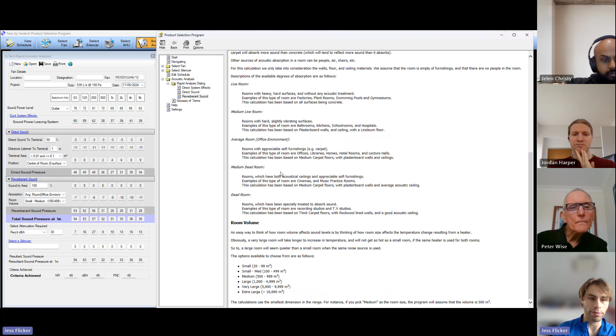And then if you need an attenuator, based on what your requirement is. So all of what we've just done is to do with the actual design of the space. But if you have a special requirement, which can be NCC or whatever the client wants, then you can put that in and select a silencer to achieve that.